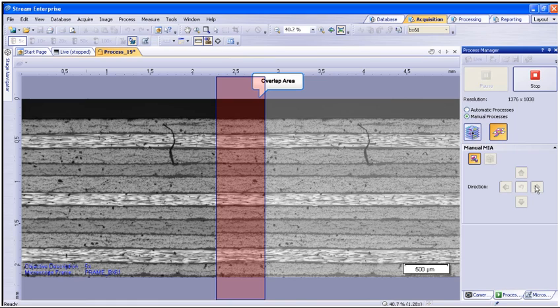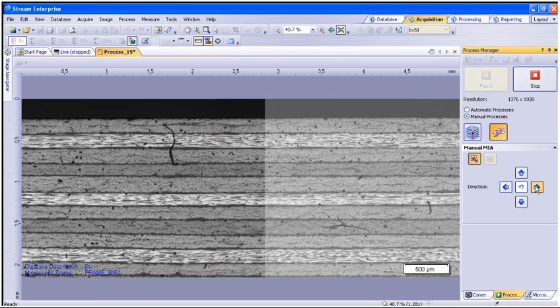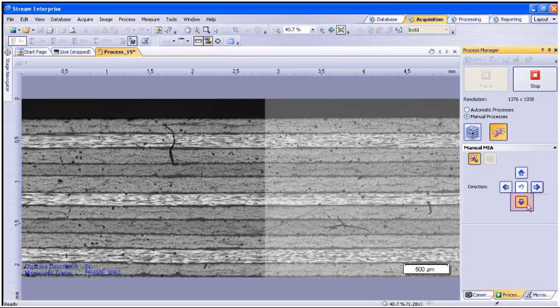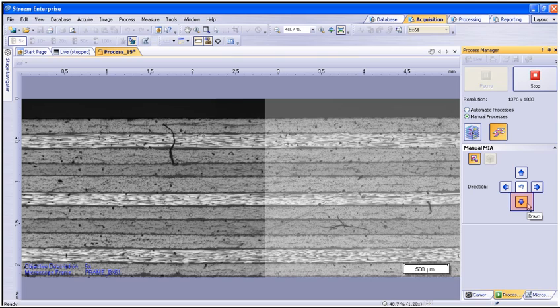You can now manually move the stage to overlap the captured image with the new live image that is watermarked. The alignment of the two images needs to occur in the overlap area. Once the overlap area is aligned for the first frame, click the down arrow to acquire the image below.